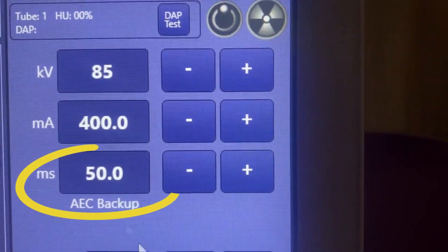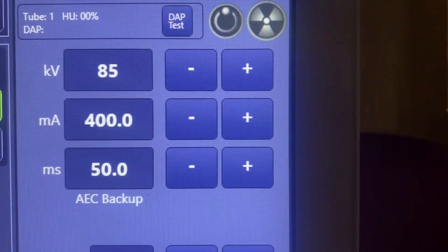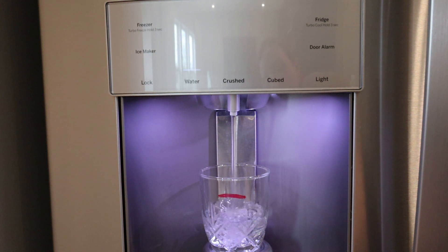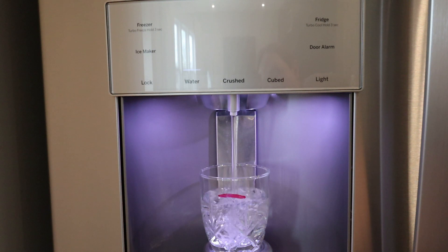The exposure will continue until it either reaches the number of x-rays it's expecting or a backup timer has been reached. The backup timer is like setting a red line across the cups — the exposure will terminate whether the glass is full or not, depending on where that backup timer is set. Backup timers are set to protect the patient from overexposure. If the refrigerator malfunctioned and the backup timer was not set, it would just overflow the cup, resulting in an overexposure to the patient.